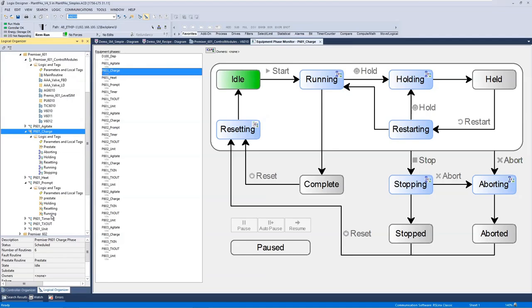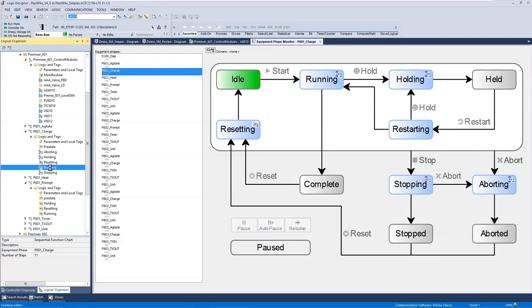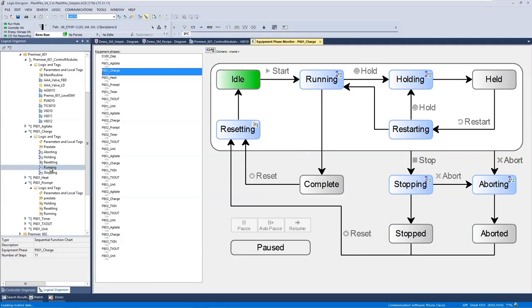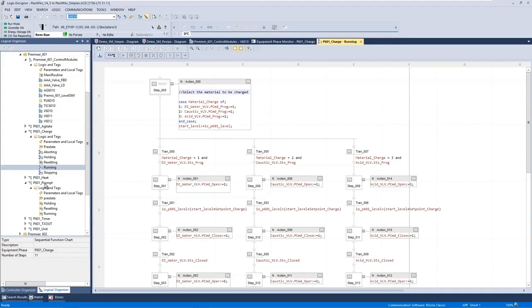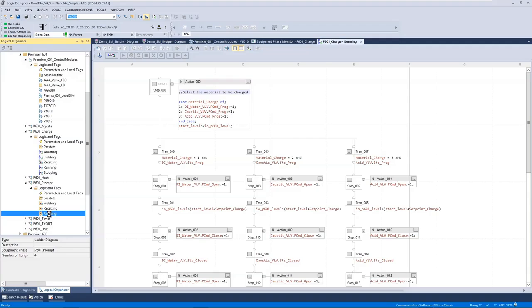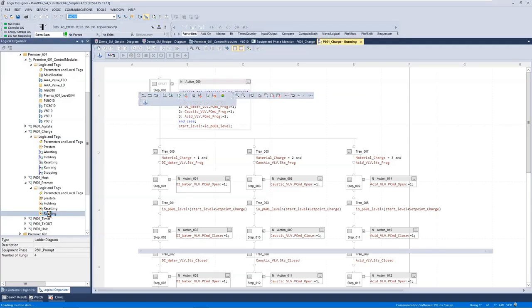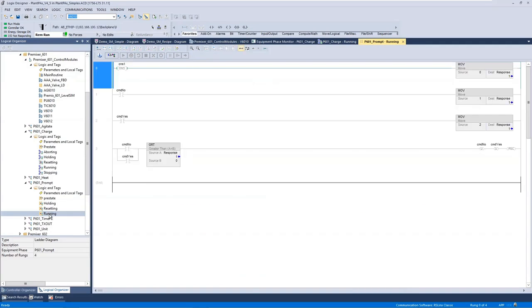Each of those steps you can then write in the language of your choice. So if we go and have a look at our charge phase, and we go and have a look at our running step, we can see that that's been written in sequential function chart. So here is an example of that code. And if we go into our prompt equipment phase, and look at that running step, we can see, as it's much more simplistic, that it's been written in ladder logic. The choice is yours.